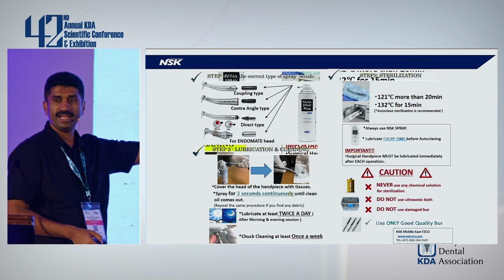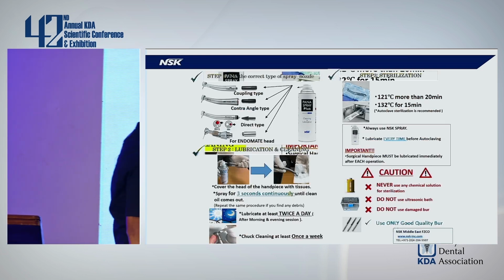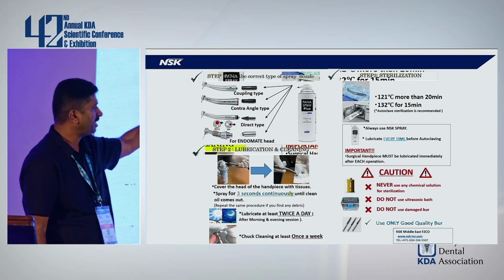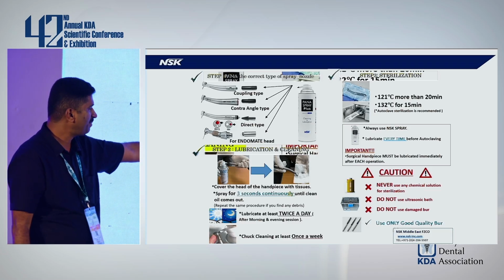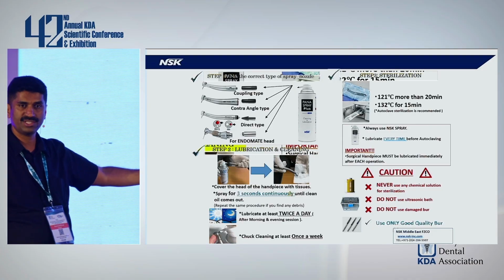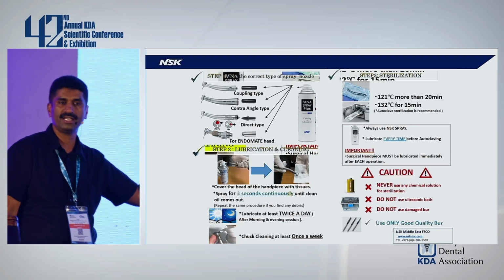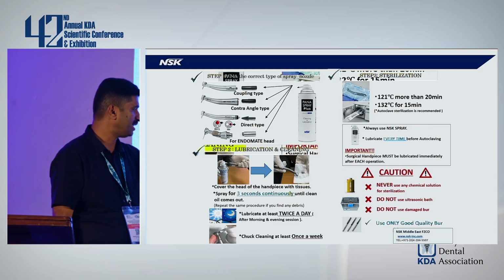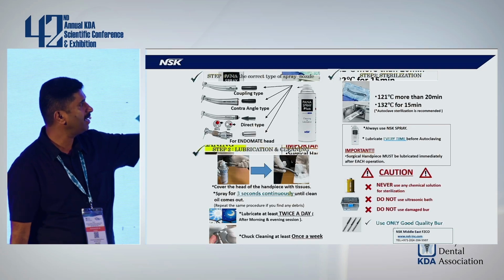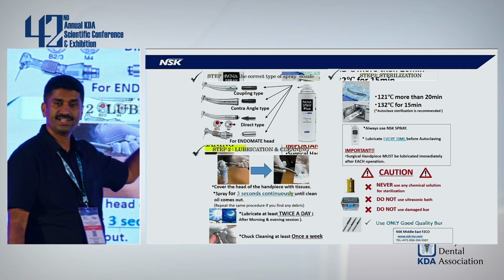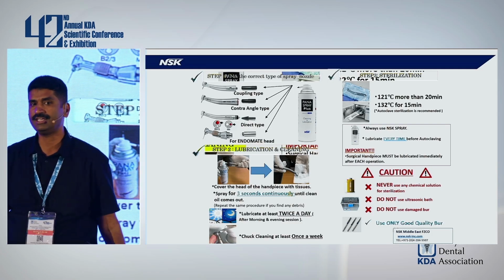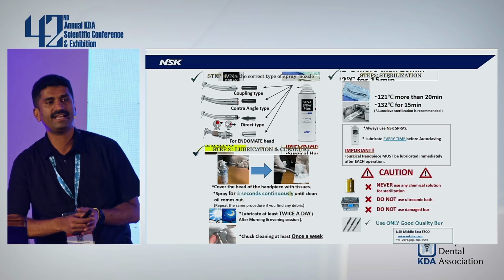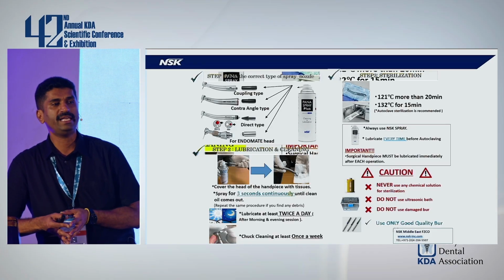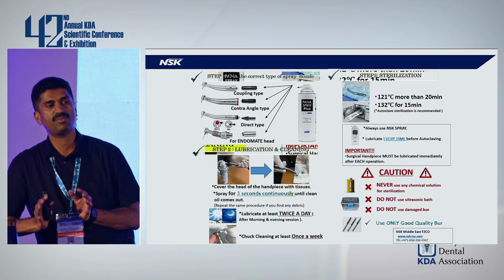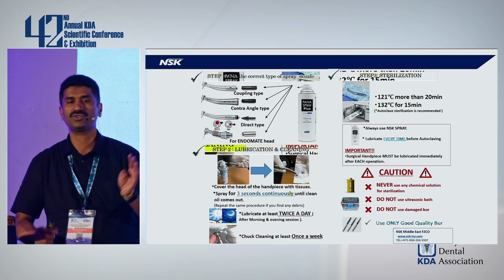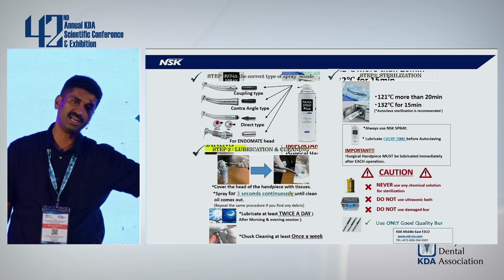So whatever I've explained is mentioned in a single sheet. Use a proper lubricant nozzle for the oil sprays. Bring the handpiece to the oil spray, spray for 3 seconds until you get clean oil coming out from the handpiece into the tissue paper. Lubricate 2 times a day. The only methodology of sterilization is autoclaving, and use good quality burs. So this, if taken care of, will cover your complete criteria of working with proper maintenance of the handpieces. So I repeat, just four things which you need to take care of.